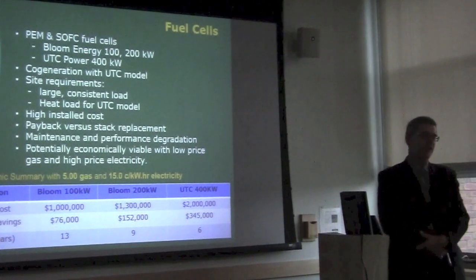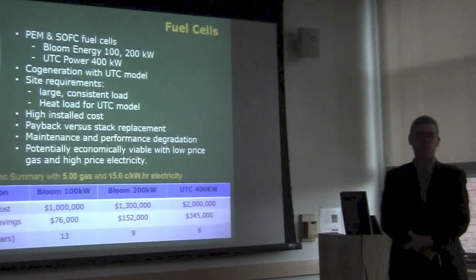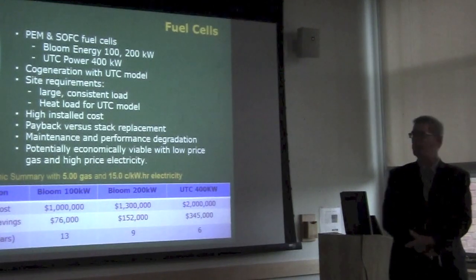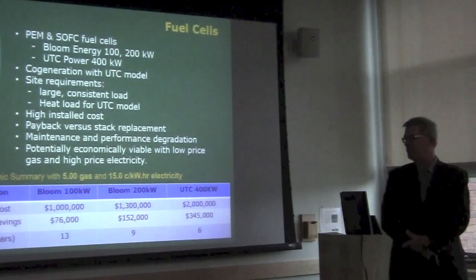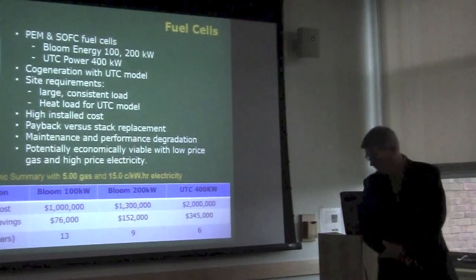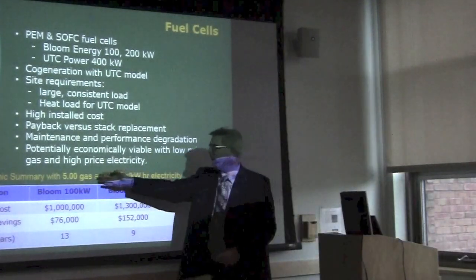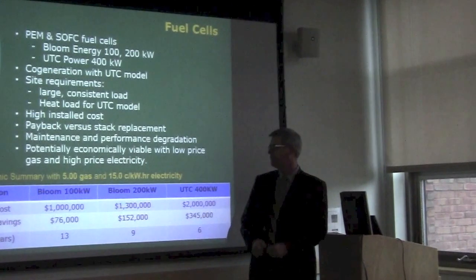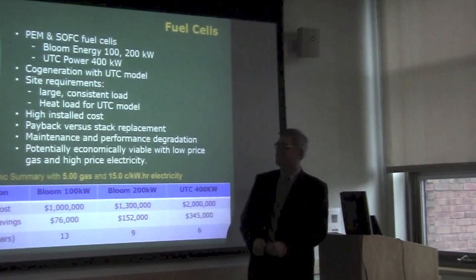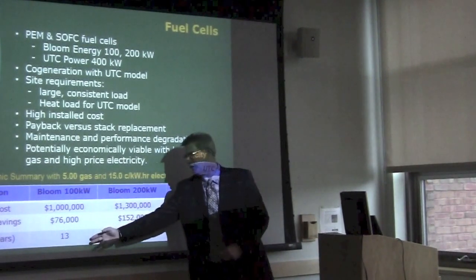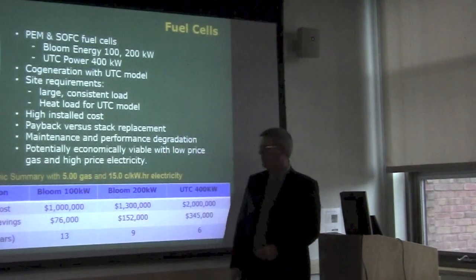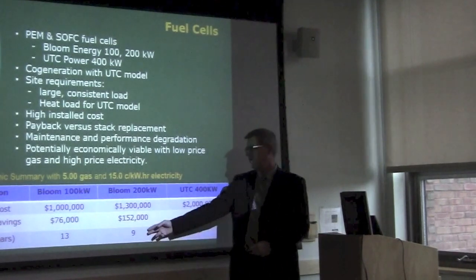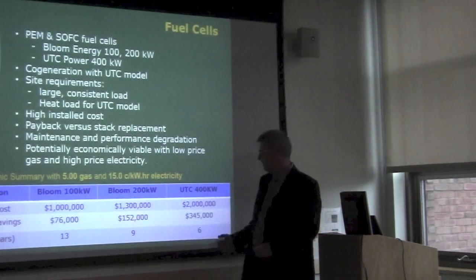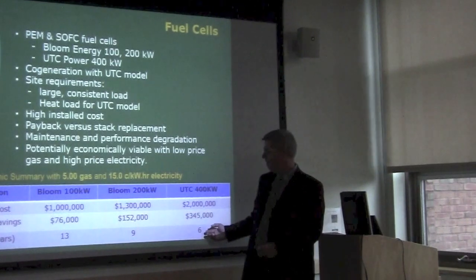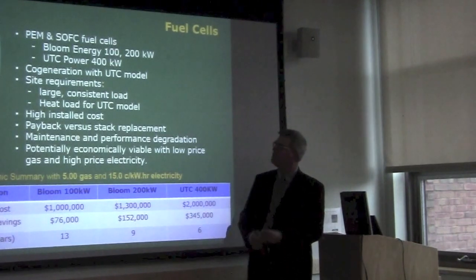They're potentially economically viable if we're looking at low gas prices and high electricity prices to avoid. In the $5 gas and 15-cent kilowatt-hour electricity scenario, the Bloom, which had no cogeneration, showed a payback around 13 years. The larger module was about 9 years, and the UTC 400 kilowatt module had a 6-year payback.